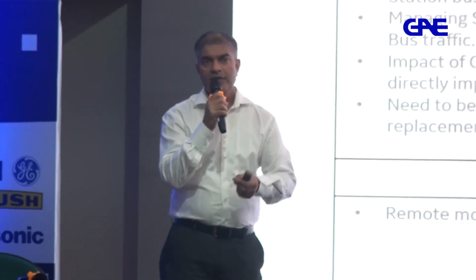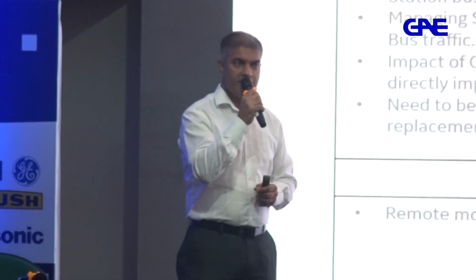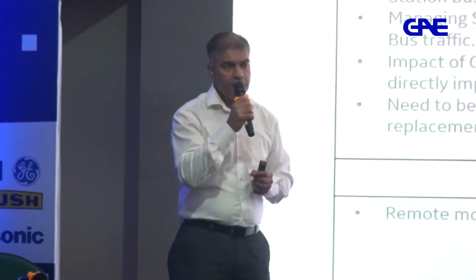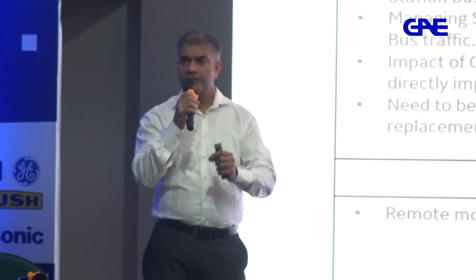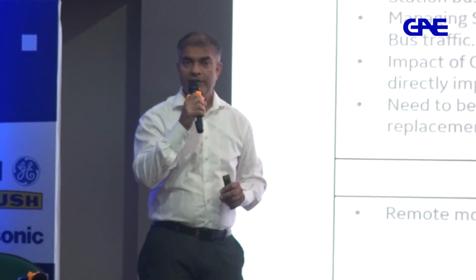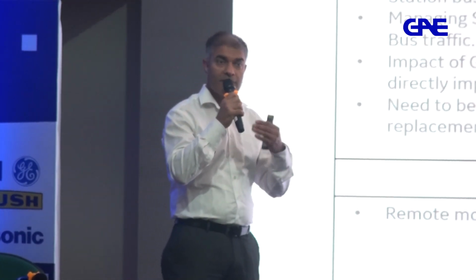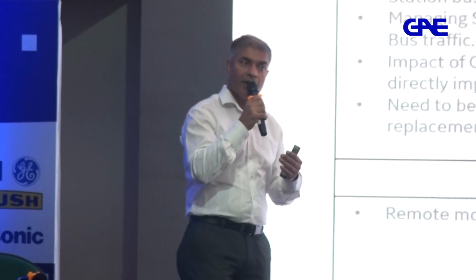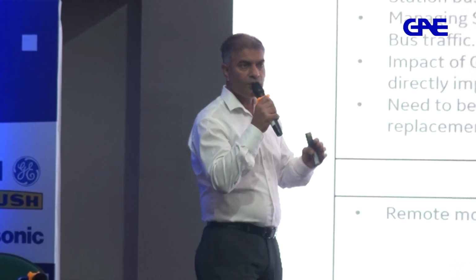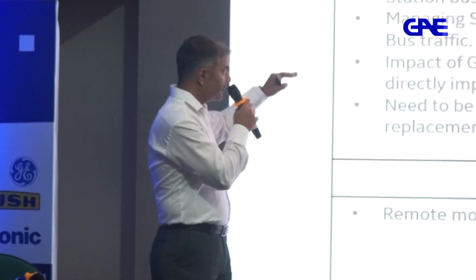The Ethernet ports of equipment are rated to see some traffic, and typically the IED ports are 100 Mbps. If you expose them to sample values, it will very soon saturate and collapse, so it will stop functioning. So you need to separate the traffic. This is one challenge.